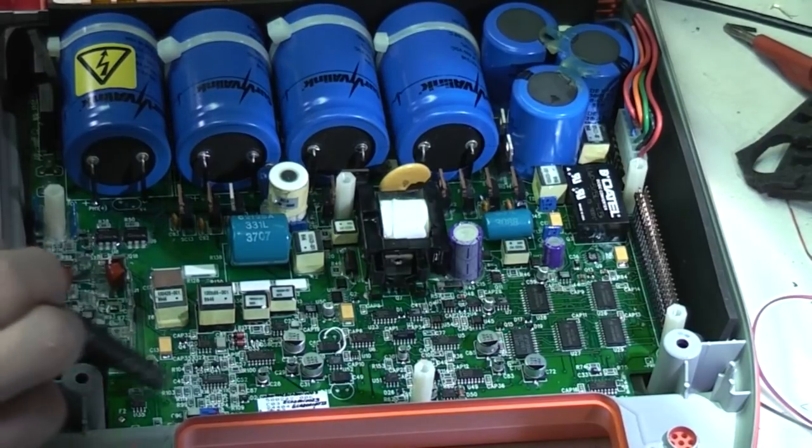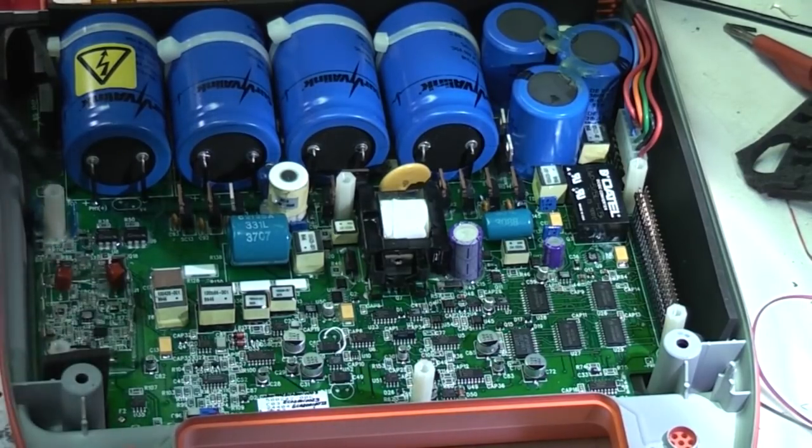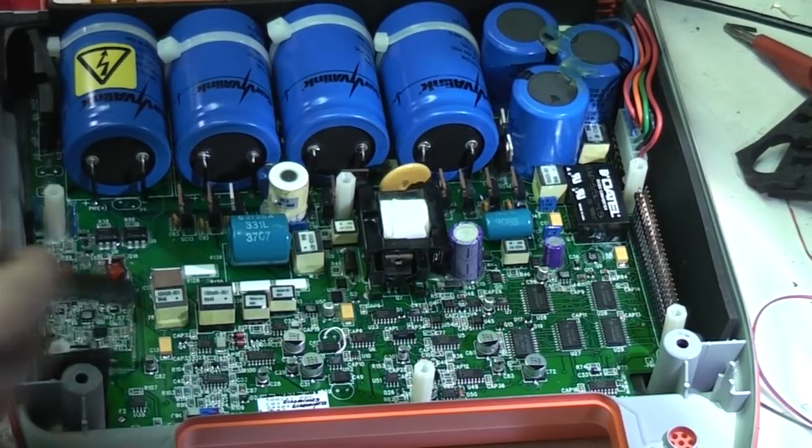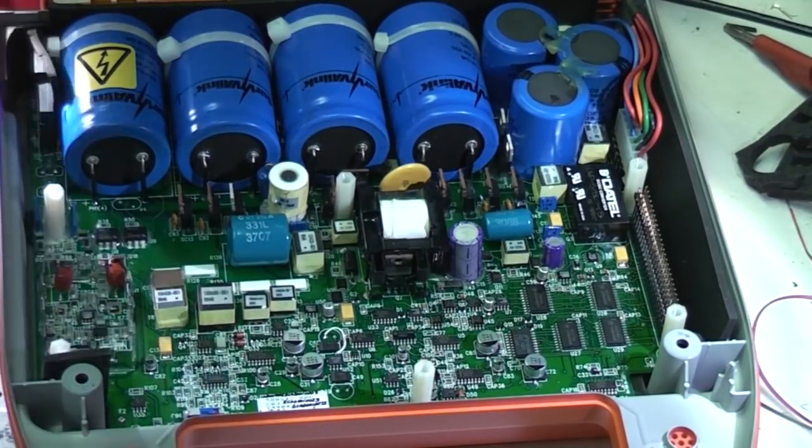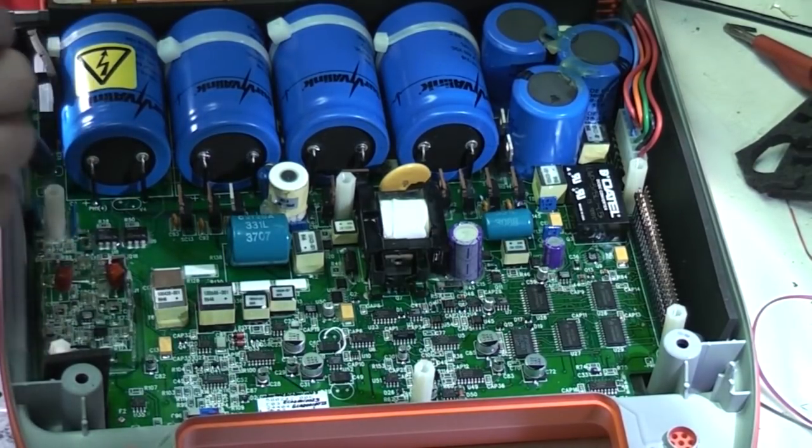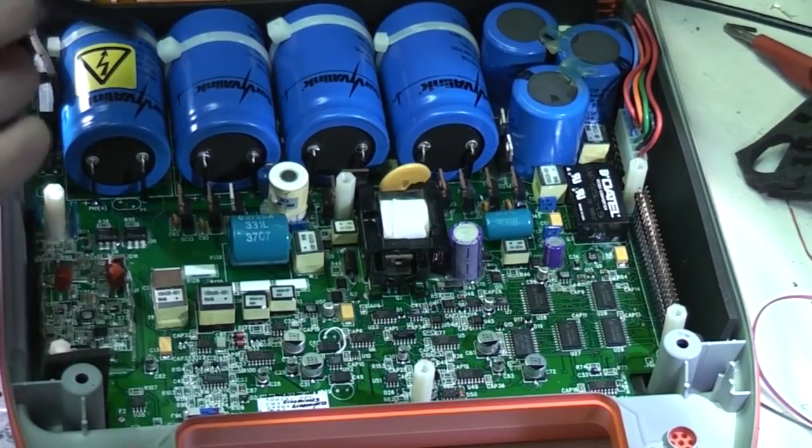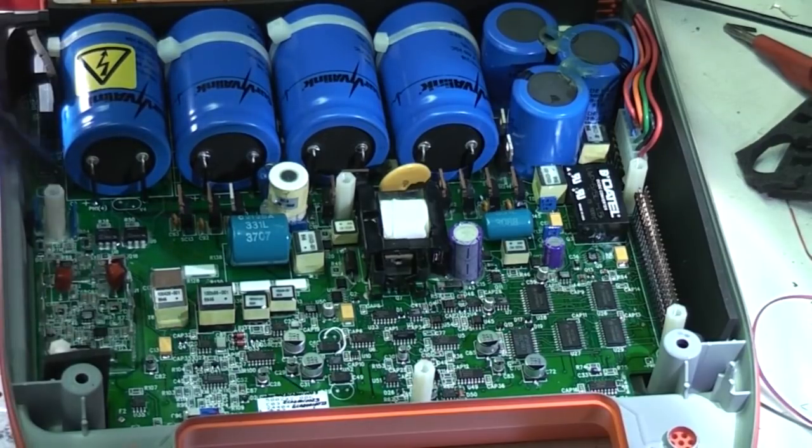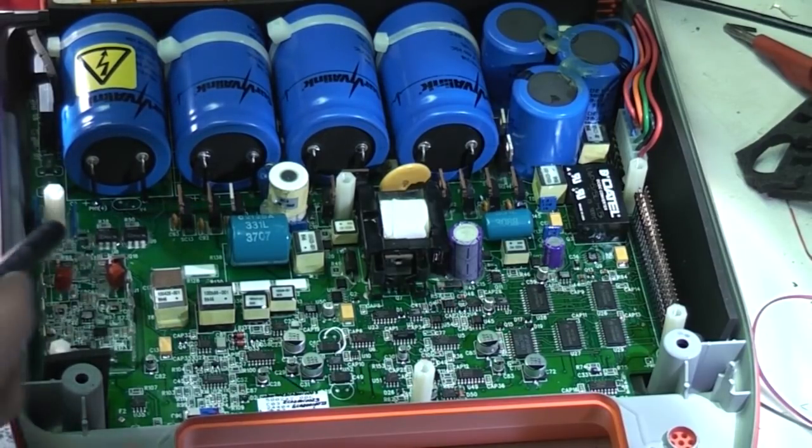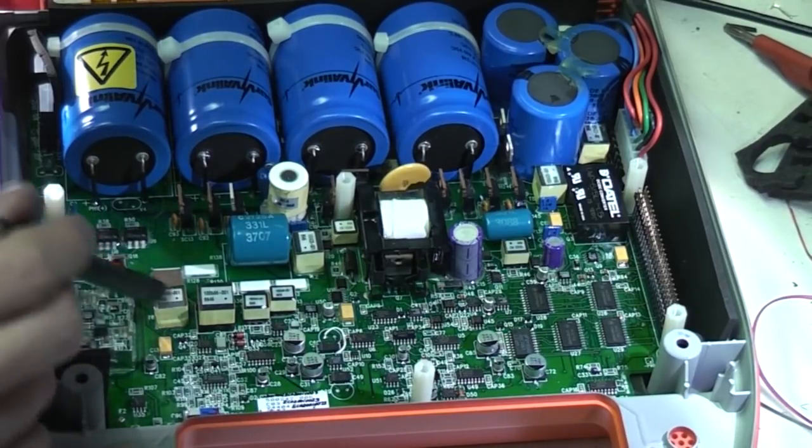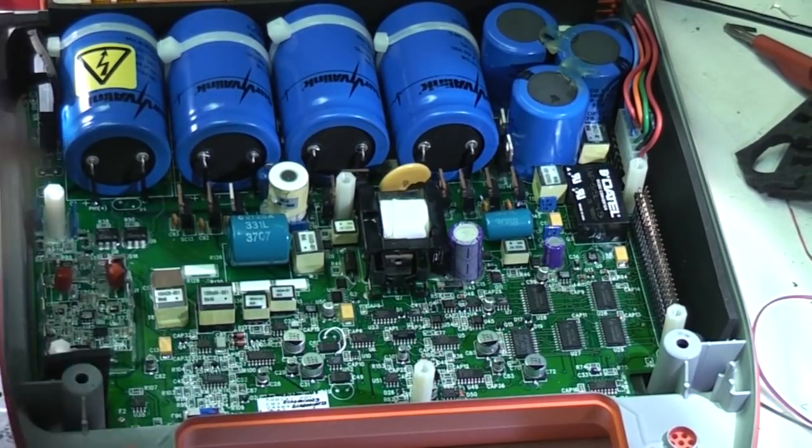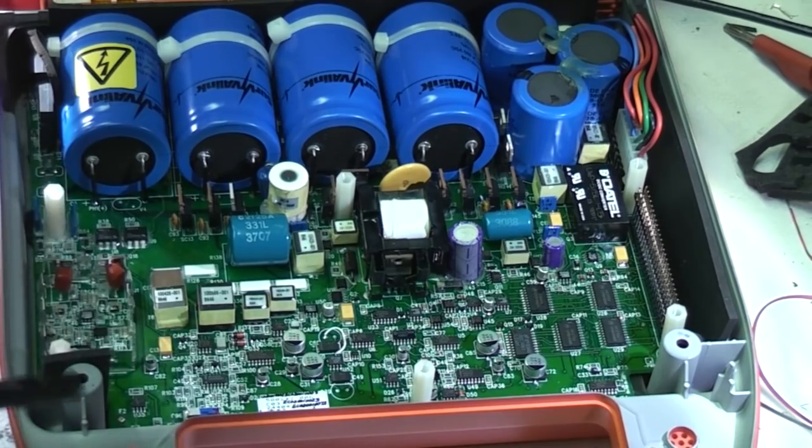I can't actually see any isolation of the analog voltage but there's some two high value resistors here connecting the patient electrodes to the low level stuff at 20k. They're quite big thick wirewound resistors so the isolation of the high voltage from the low level is probably mostly through those 20k. There's obviously going to be some clamping diodes and all that sort of stuff to protect it from when it delivers the high voltage, just to avoid blowing up its front end.